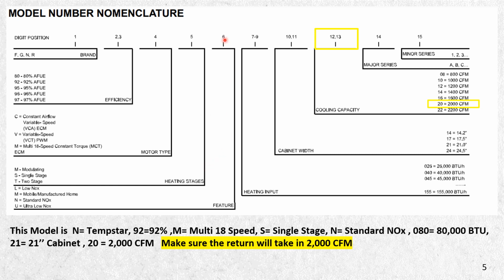And then in the next position, the sixth position, we have standard NOx, the N. And then in our heating input, 7 through 9, you'll see over here the BTUs. This one is an 080, so it's 80,000 BTU. Then the next group of numbers, the 10th and 11th numbers, is 21. So we have a 21-inch wide cabinet. And the 12th and 13th is our cooling capacity. So it's a 20, so this refers to a 2,000 CFM. And so we have a 21-inch cabinet that is 2,000 CFMs, and it puts out 80,000 BTU.